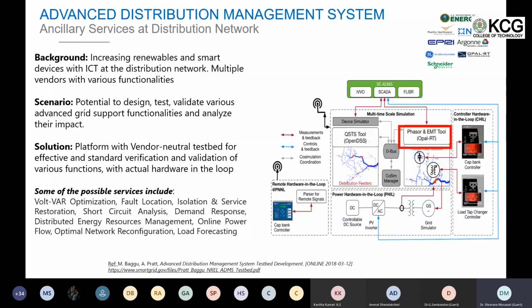What was done here: a load change and other phenomena were created, and it was observed what impact these changes have on volts and vars on one particular feeder. Then it was shown how the DERs, in this case the solar inverter, can actively contribute to improving voltage regulation, or supply the necessary reactive power to improve voltage regulation at that point of connection. Yes, there was a certain improvement.